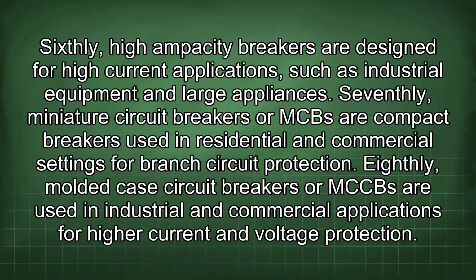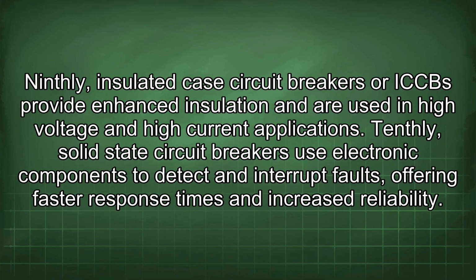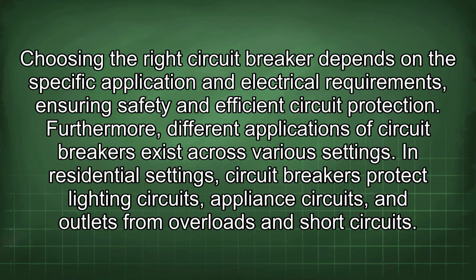Eighthly, molded case circuit breakers or MCCBs are used in industrial and commercial applications for higher current and voltage protection. Ninthly, insulated case circuit breakers or ICCBs provide enhanced insulation and are used in high voltage and high current applications. Tenthly, solid-state circuit breakers use electronic components to detect and interrupt faults, offering faster response times and increased reliability. Choosing the right circuit breaker depends on the specific application and electrical requirements, ensuring safety and efficient circuit protection.